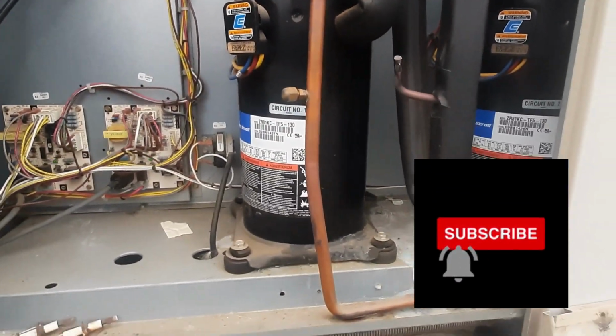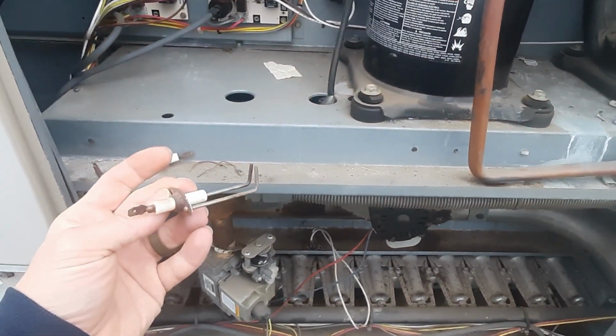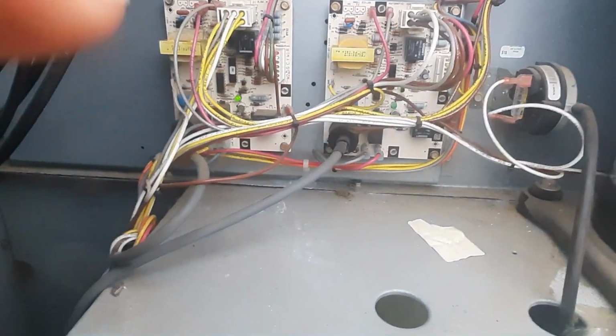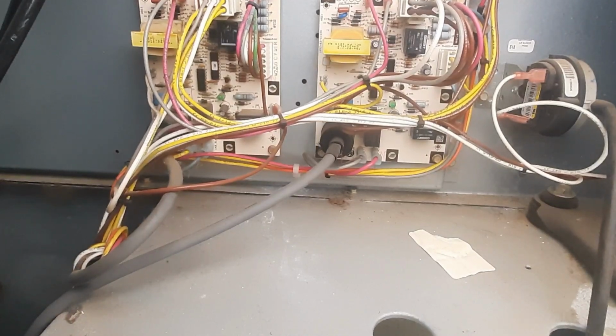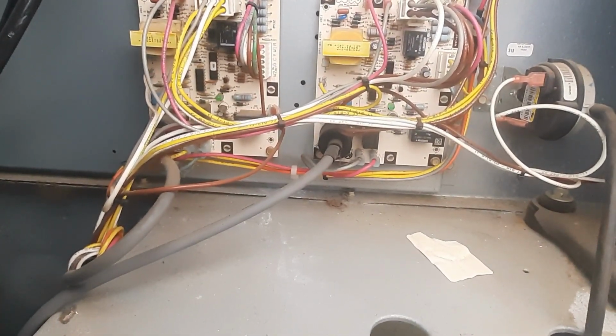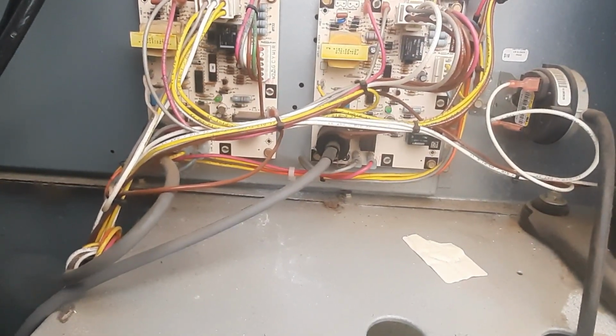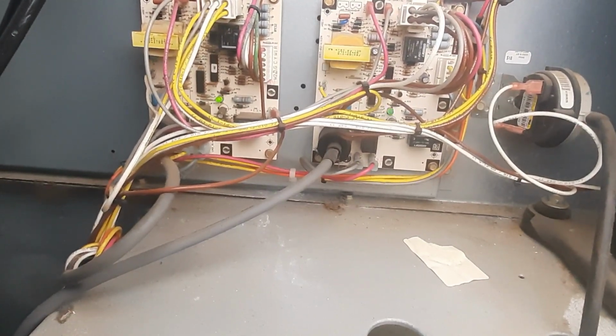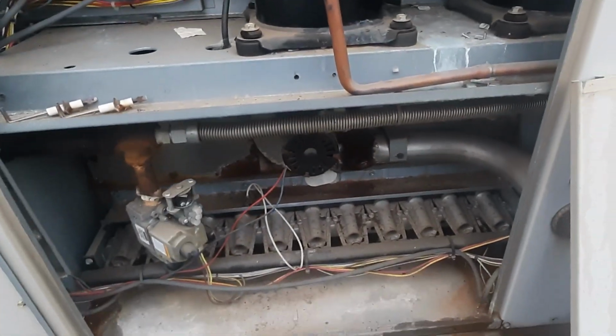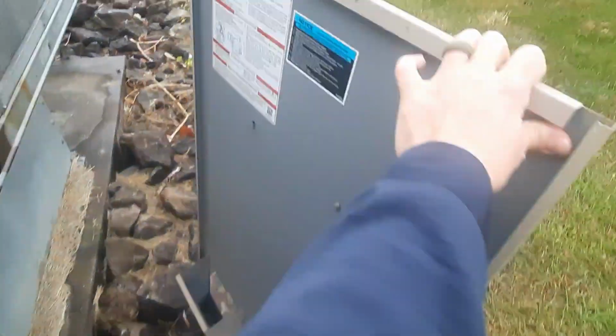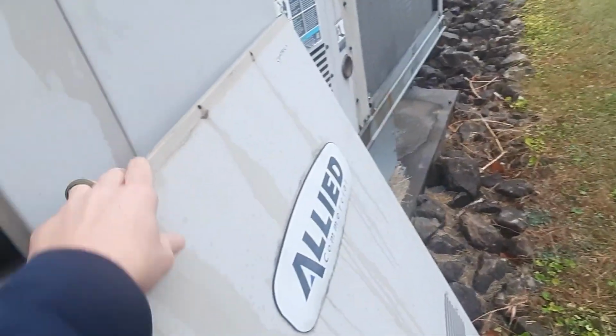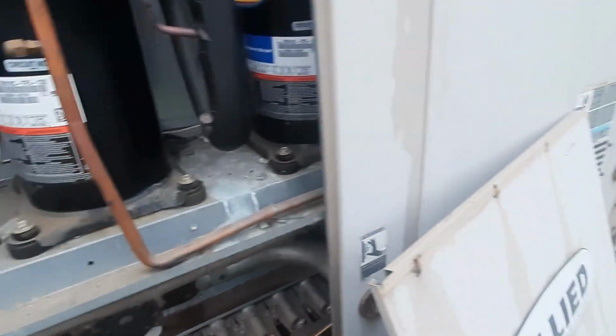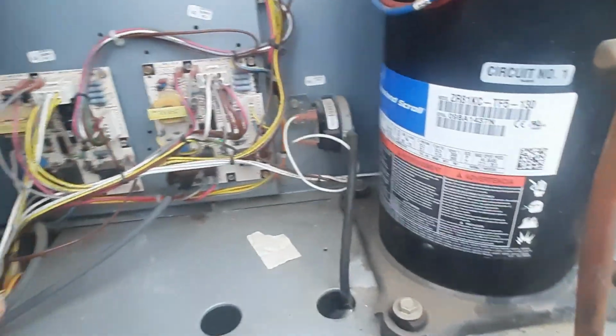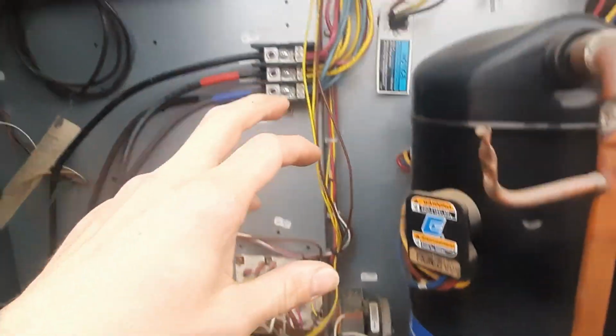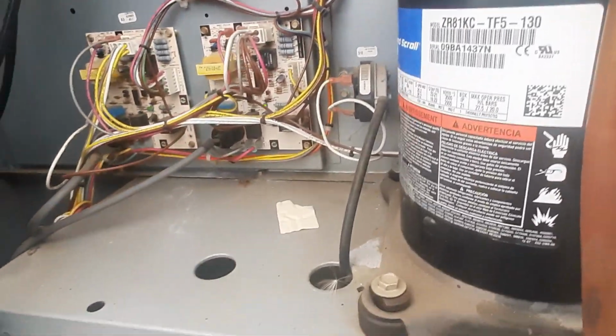Nothing too out of the ordinary here. Kind of noisy blower contactor. Like I said, we do have a maintenance due on this. It's like somebody's changed the spark igniters. And it looks like I'm getting four flashes. I'm getting four flashes out of both of them. I don't know what that means. It's not on there. So, like I said, that stage was fired. So maybe four flashes is a delay of some sort. Let's make sure we got a call because it hasn't kicked in yet, and then try to find out what that flash code means.